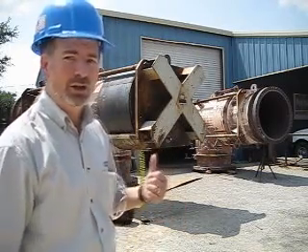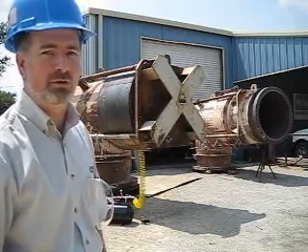Right behind me are two Westinghouse crossover steam turbines. We received these in and we did exactly that. We fixed them in a special way, we put the test heads on, we cranked them up to the high pressure, and we ensured that they were good, and they were then validated for that higher pressure. And now we're shipping them back to the utility.